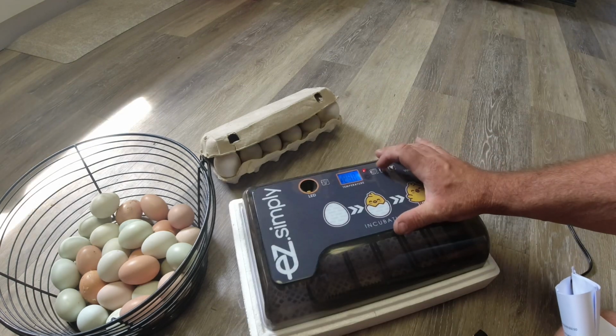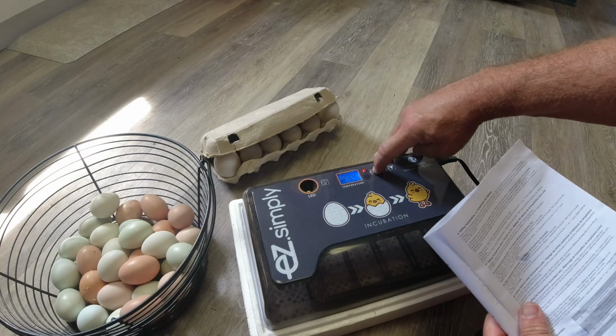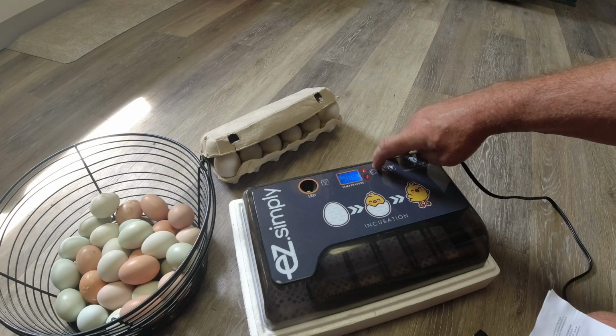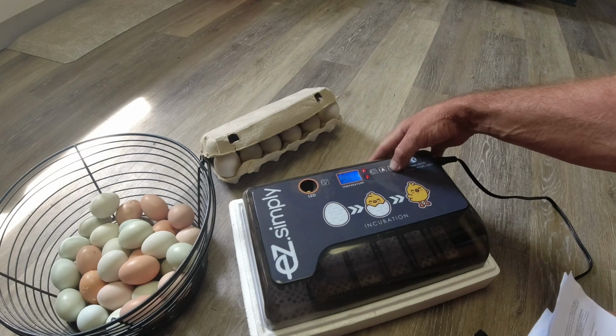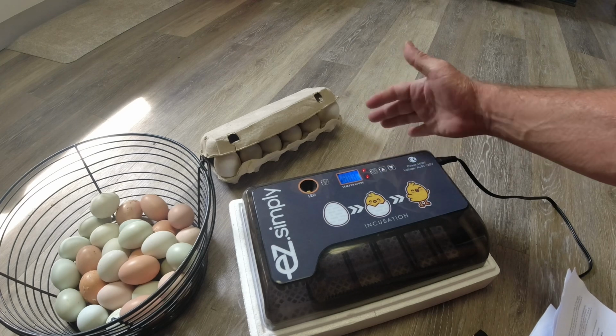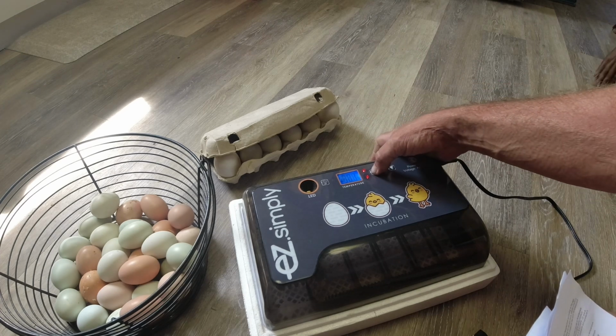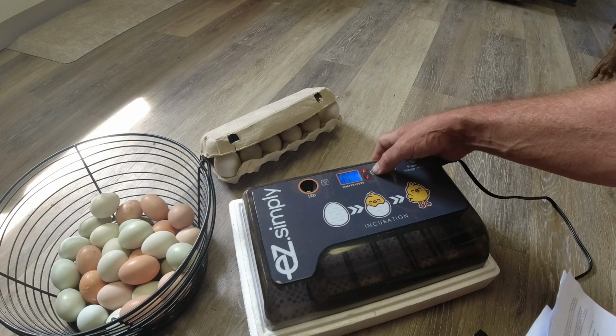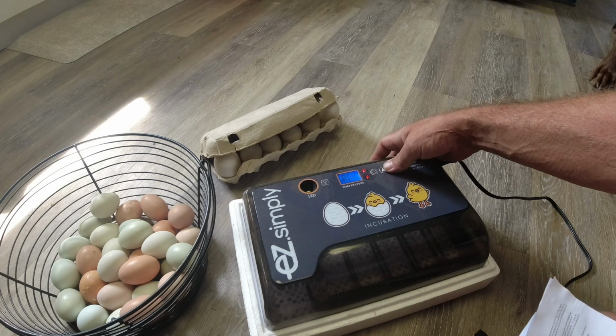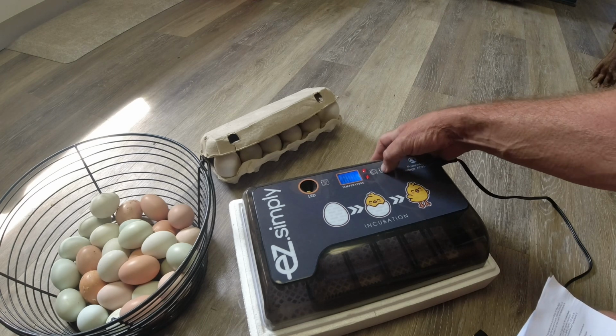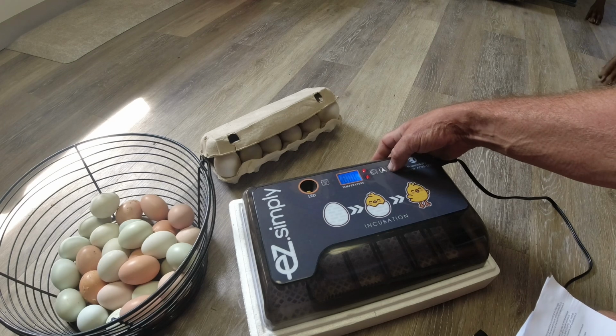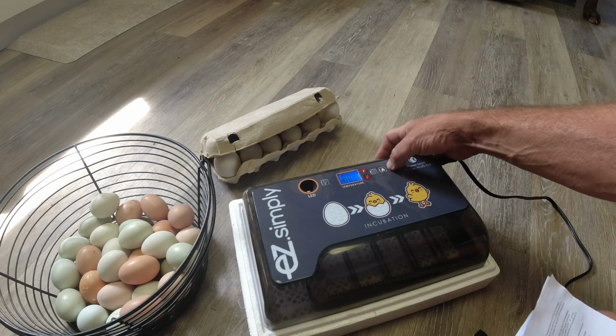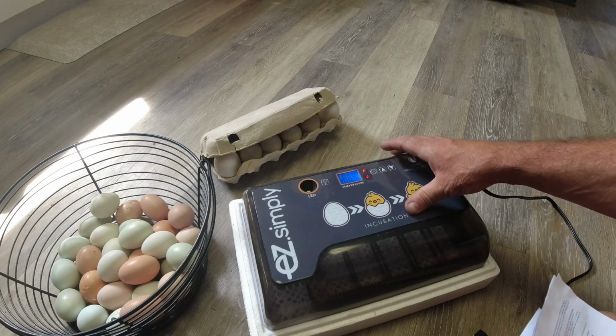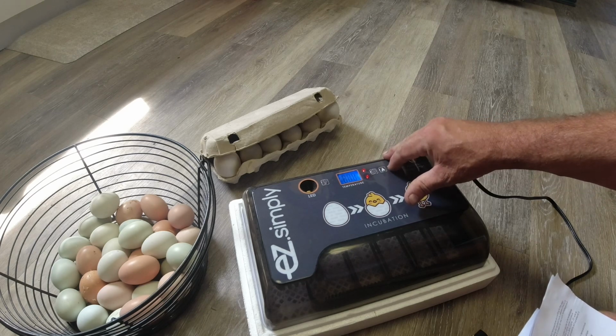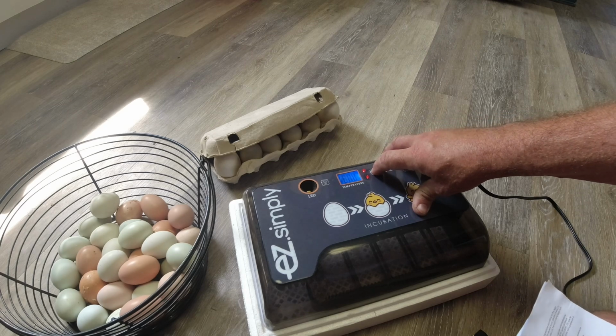There are a lot of settings for this, and this is the settings button you can push right here. First of all, you can just set your temperature wherever you want to put it at, 38.7. Now if you hold it down, you can set an alarm low point, which you can make 1 degree. If it drops 1 degree lower than your setting, it'll go into alarm. And you can do the same on the high. If it goes half a degree higher than where you set it, it'll alarm.